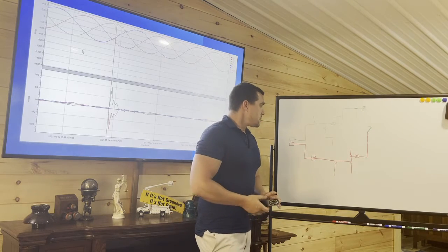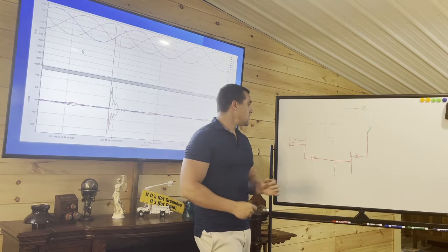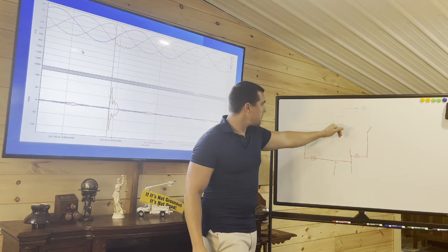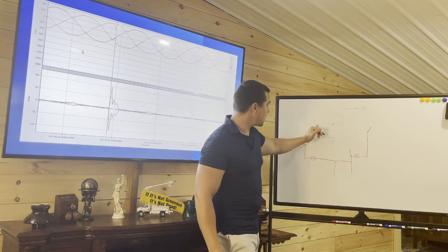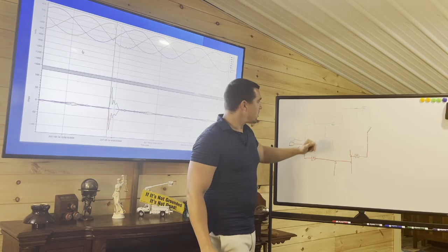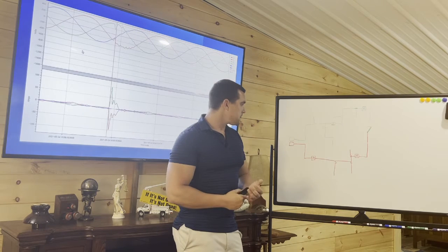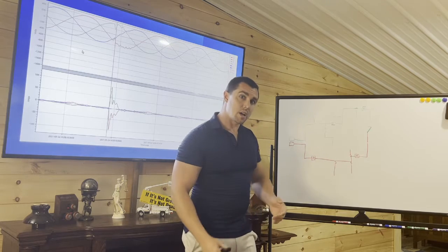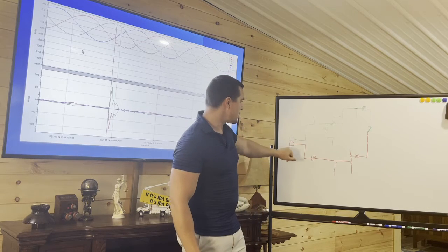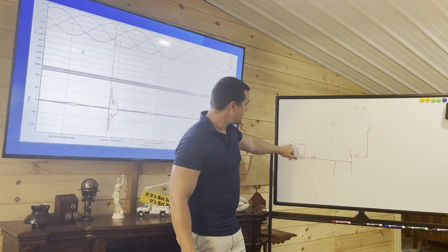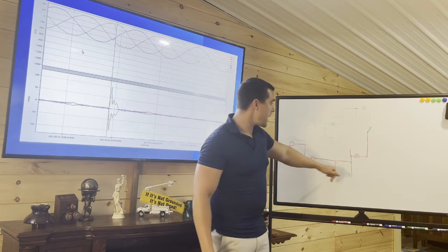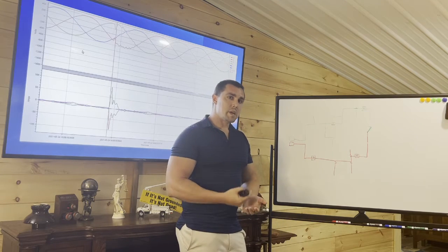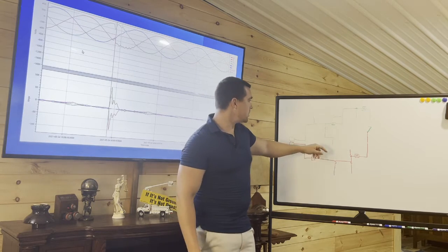One other thing I wanted to speak on is to our system planners. As I mentioned earlier, in our scenario, red feed would feed up to the first recloser if the fault was seen here. So your fuse coordination, it's all fault current based, fault current being provided from the substation or the source. So if you change your source and the path to the fault, your impedance in your line, you may not have enough fault current to blow the fuse.